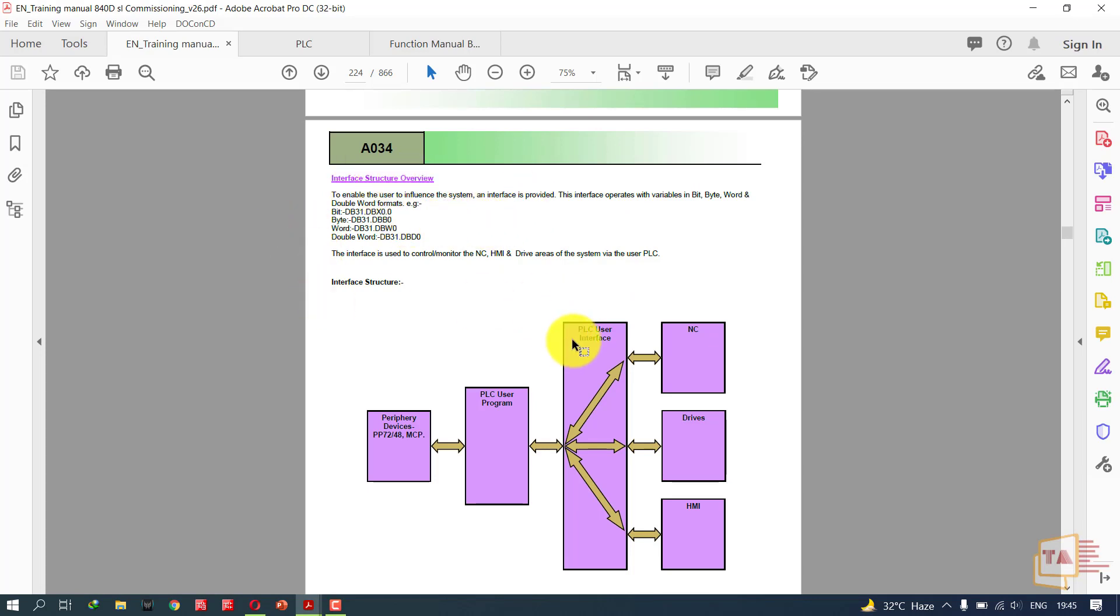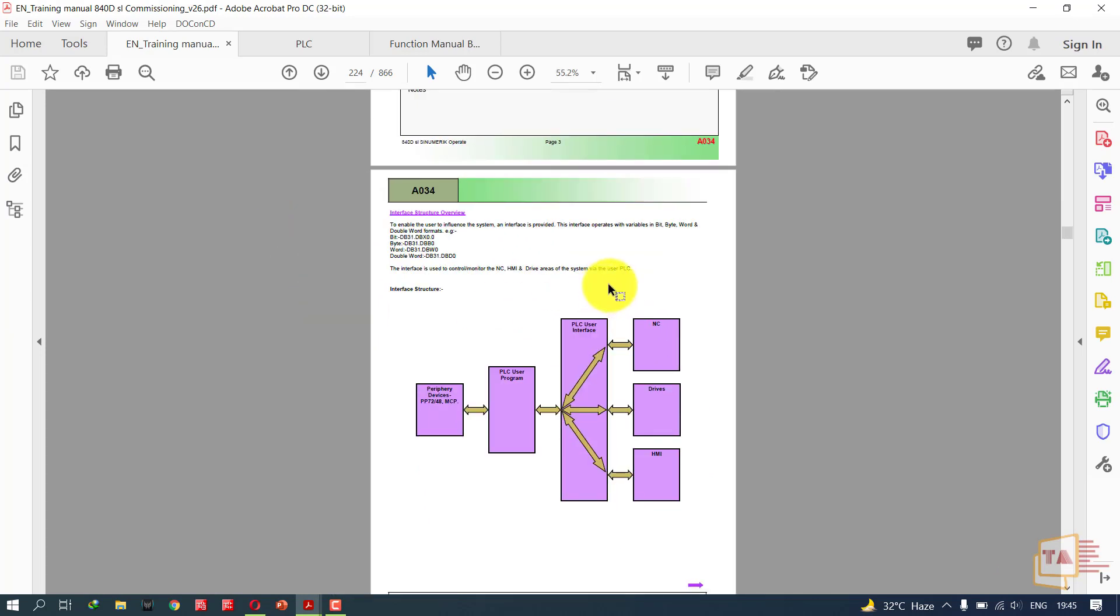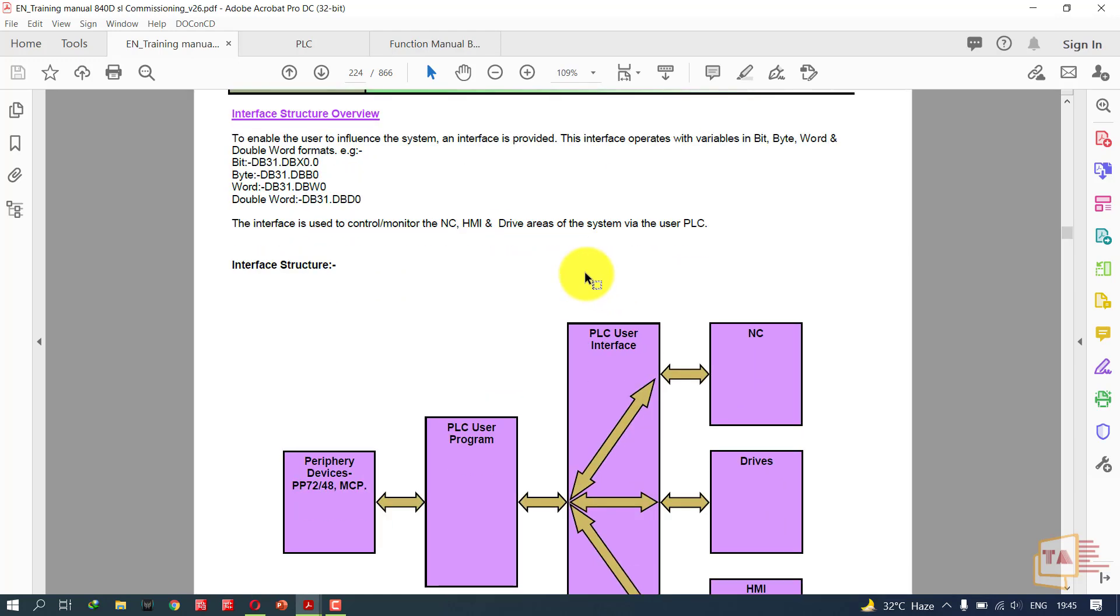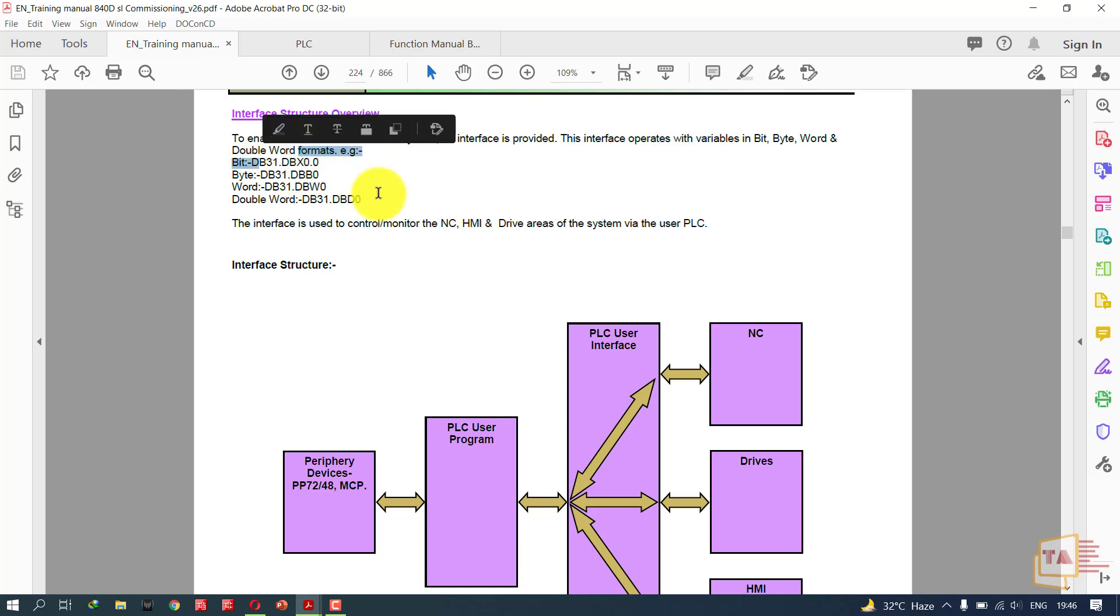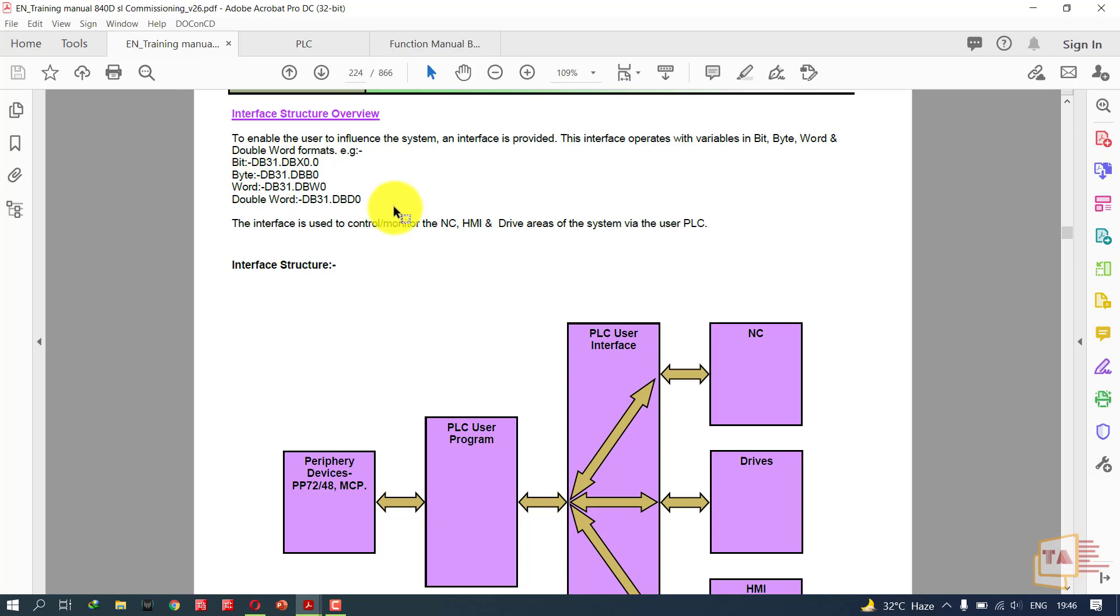This is the PLC interface structure. To enable the user to influence the system, an interface is provided. If you want to influence the system or modify the values or variables, you can use the interface in formats like bit, byte, word, or double word. For example, if you want to activate DB31 DBX 0.0, you can use the fields in PLC interface structure. These bits are communication bits we can use to communicate with the NC, drives, HMI, and so on.